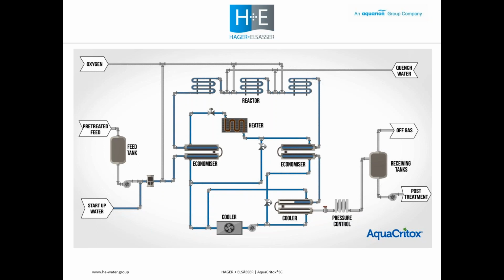The heat exchange and reactors are all built with highly corrosion-resistant nickel alloys. And once a system has been pressurized, heating begins through an electric heater. The central loop you can see here is isolated from the main process and uses water as a heat transfer fluid. This system operates around 88 bar. This system is used to heat the fluid now entering the package, and the heated water passes through the reactor.